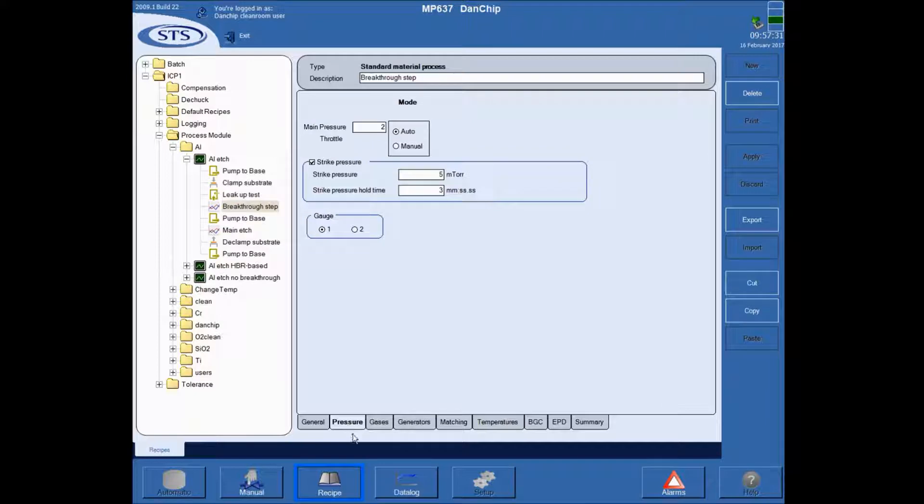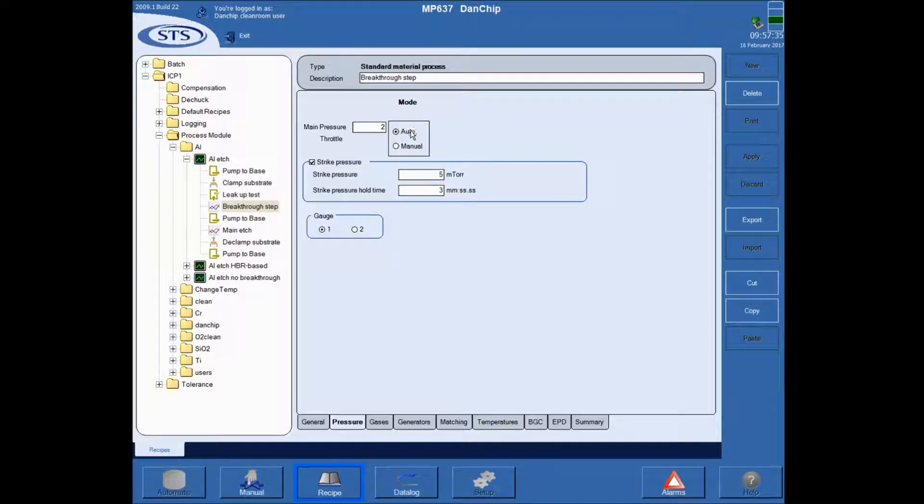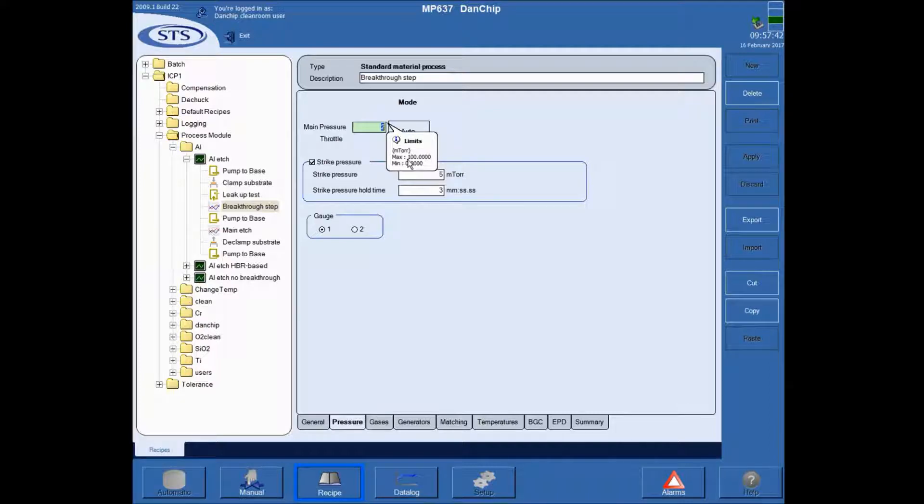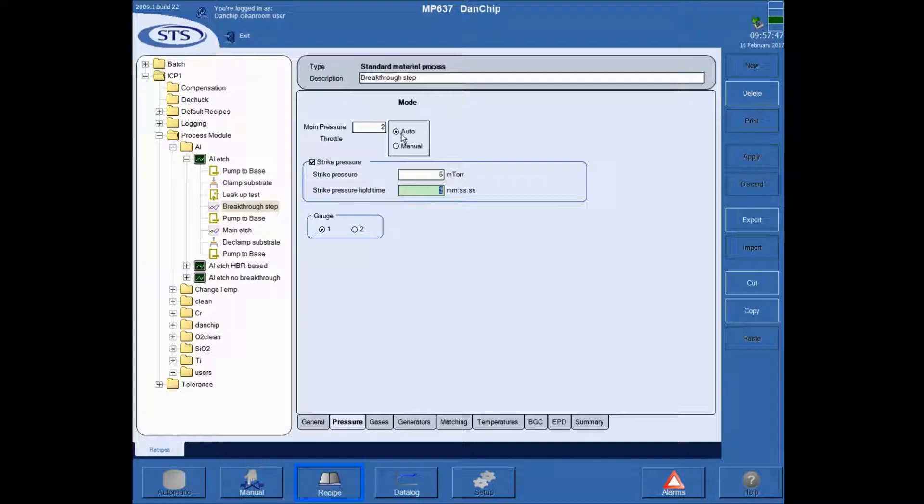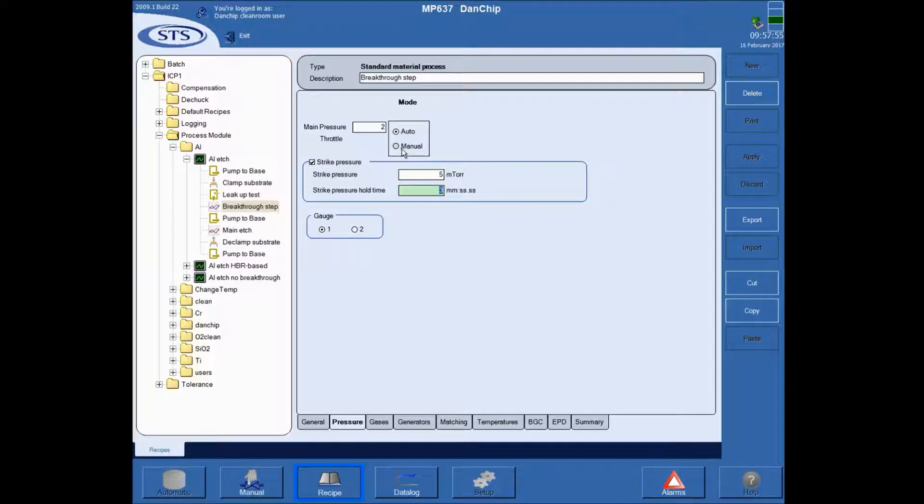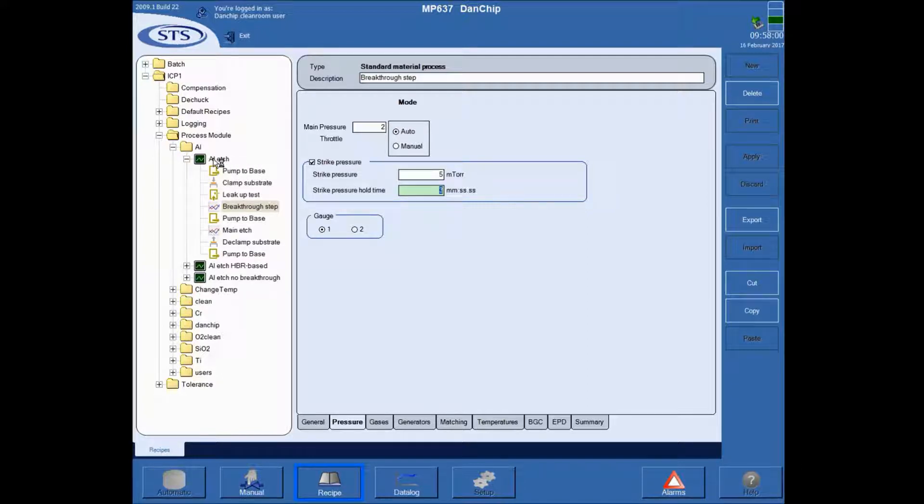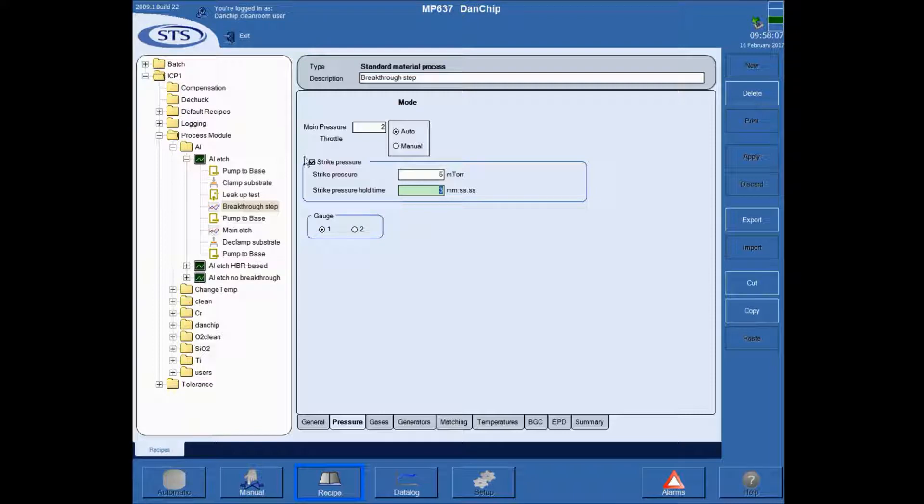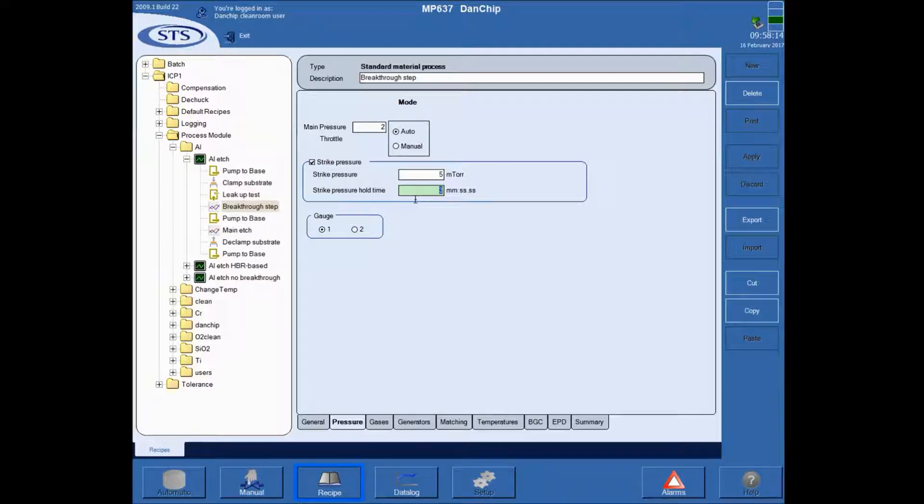Under pressure, you have the pressure setting. You can either use automatic, that means you have a setting. I double-click to see the ranges. You can either do auto, in which the APC valve will try to match a certain pressure in millitorr, or you can set the APC valve at some fixed angle. In this case, with the aluminum etch, the pressure is very low, so in order to strike the plasma, you will have to use this strike pressure, which is slightly higher for three seconds, and then it will run fine after that.